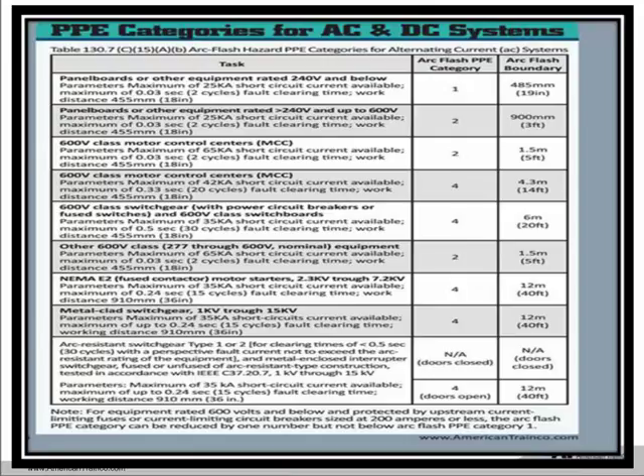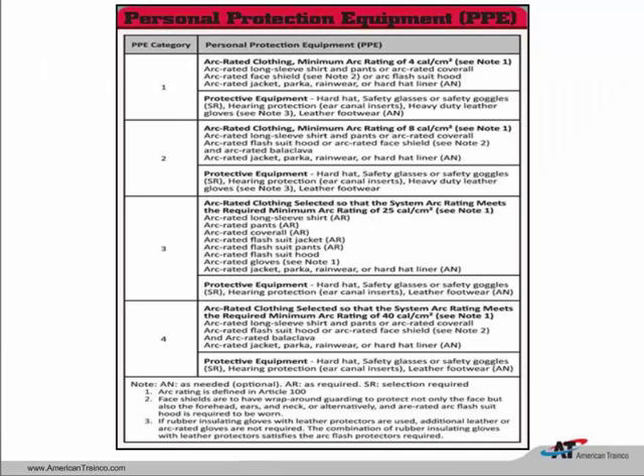So this table is used in conjunction with the previous table, also in conjunction with the next table that I'm going to show you. Remember, these are snapshots of the tables. These tables do have much more equipment inside of NFPA 70E 2015. So the next table, again, they deleted arc flash PPE category 0, so we won't see that anymore. We do have to wear arc rated clothing according to the table method. Remember now that this PPE category method that we are looking at right now cannot be used in conjunction with the analysis method. This is a completely separate method.